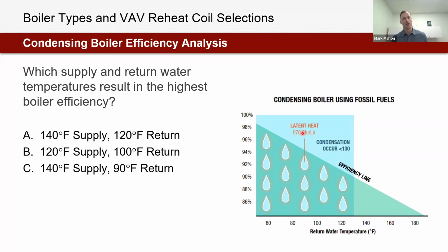And so when we get that different return water temperature back, it's maybe creating a lot of downstream design work. Now, if we could just start with 110 return water temperature or 100, we're going to have more optimally laid out and designed single duct units. We're going to have smaller distribution piping. We're going to have lower operating costs for the building, and we're going to have a happier owner. So I think the real shift is, let's just assume a larger delta T from the hop with condensing boiler systems. And that would be my advice. If I was the engineer of record, what would I do? I would have more of a 35 or 40 degree delta T for design day. And if I was a consulting engineer, I'd be yelling to my boiler guys.